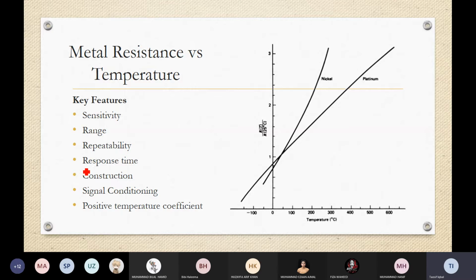Then we have the response time. When we apply a temperature, the change in resistance occurs in a very short period of time. Therefore, the response of the transducer is quite good. Its construction is quite simple, and then we can provide signal conditioning so that we can detect the actual temperature without any error. The temperature coefficient is positive. That means if the temperature rises, the resistance rises as well. So a rise in temperature results in a rise in resistance, and therefore the temperature coefficient is positive.